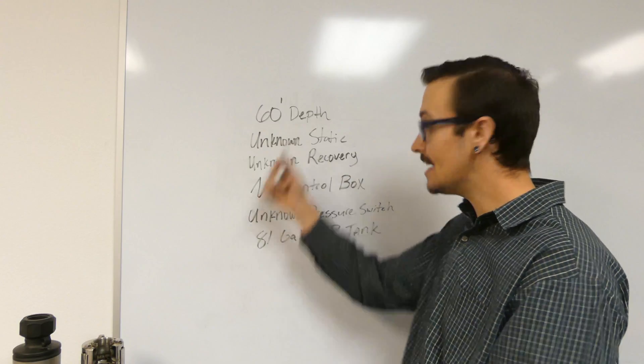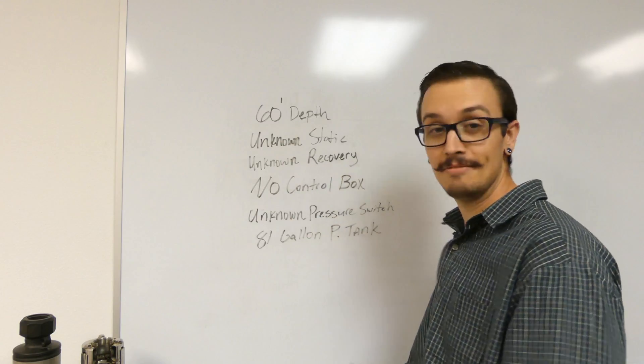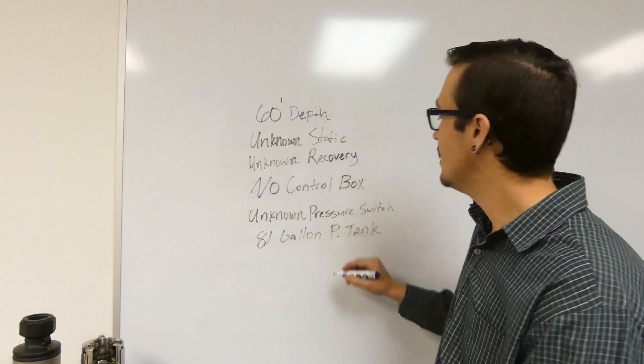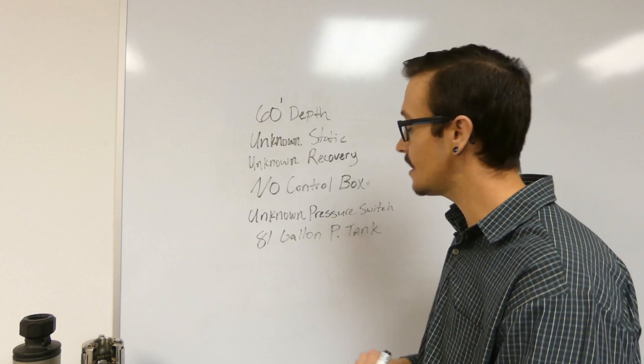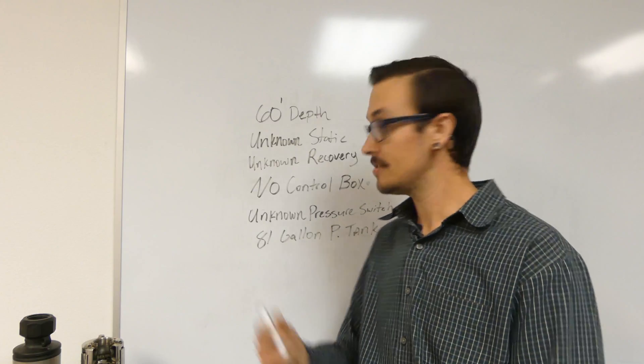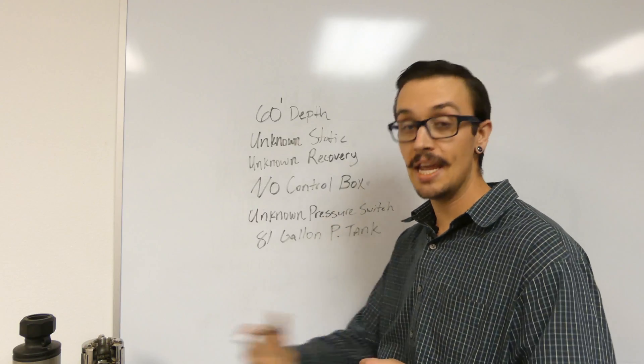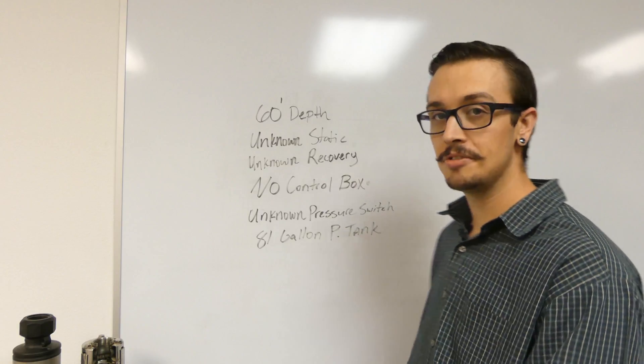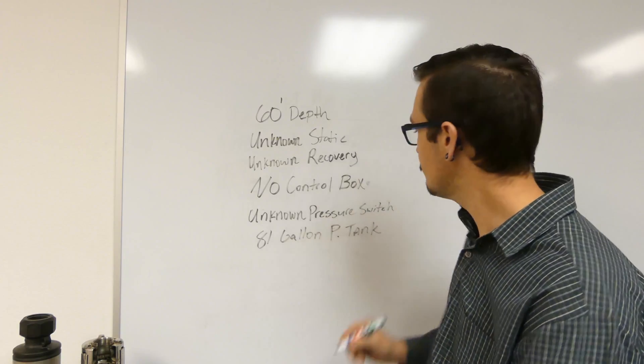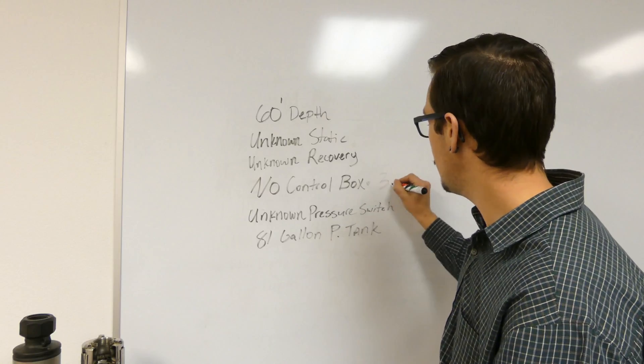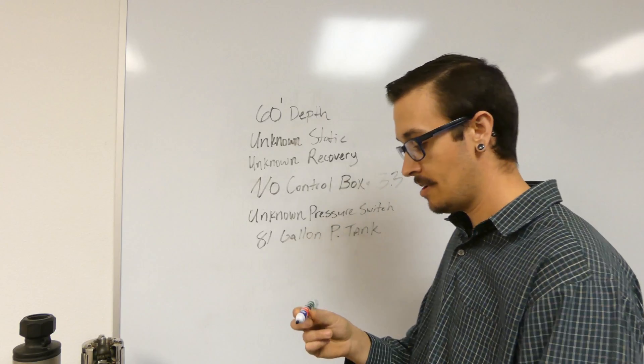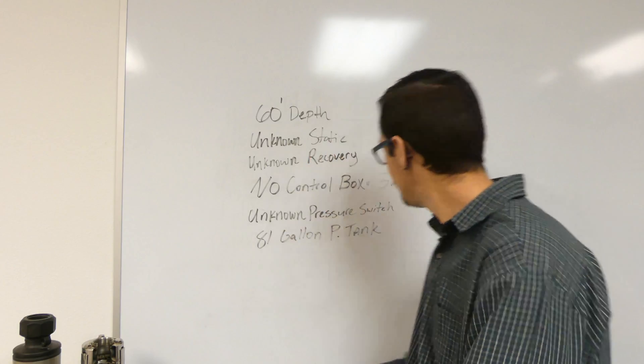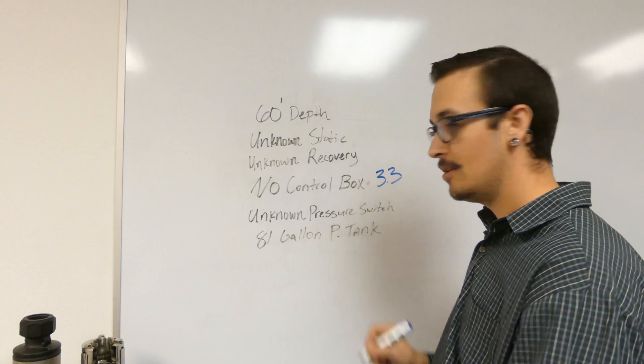So it might seem like you can't figure out what the heck pump you've got, but let's figure it out. Okay, so no control box - how do we address that? Well, we're going to take a resistance reading because in this situation we're going to pretend that the pump's dead and we can't run it to take an amp reading. So we're going to take a resistance reading. We get 3.3 ohms.